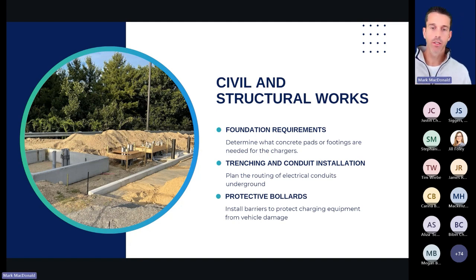Then probably the most difficult piece for most contractors would be the civil and structural work, unless they have this in-house already. But there is civil and structural work typically that needs to be deployed on DCFC chargers that we don't see on level 2 chargers. You've got to look at the foundation requirements of that DC fast charger. What size concrete pad do I need? What are the footing sizes? What are my lag bolts going to look like, or my anchor bolts, to make sure I get that deployed there? Do I have the appropriate equipment to move the fast charger once it gets to site?